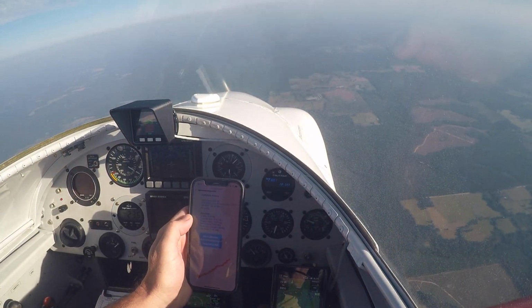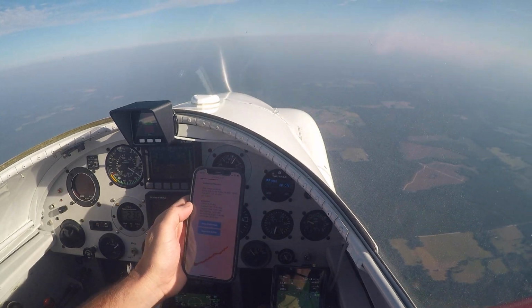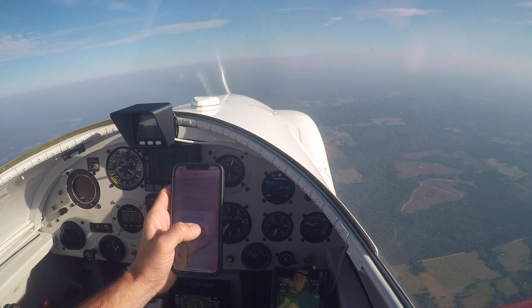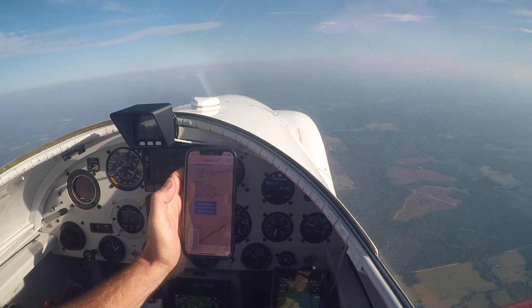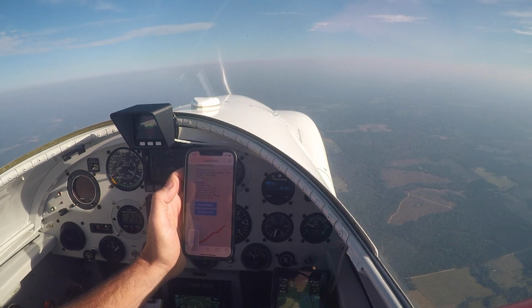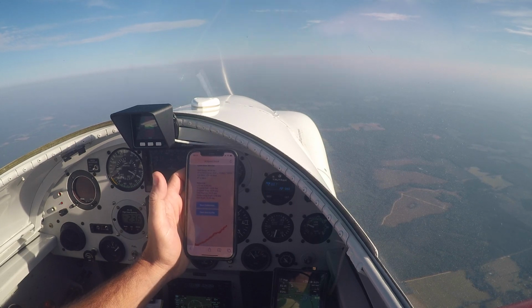And look down at our curve, and we can see we captured a good curve. Okay, we got a value of 0.9853, nice and concave. And again, we always want to save the data to the file in case we need any sort of tech support.